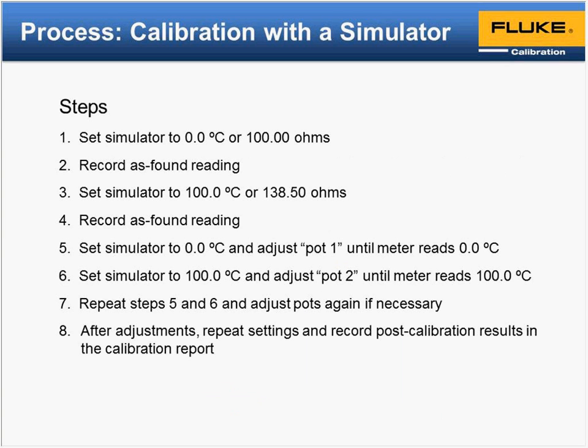Establish the connection. The routine is pretty easy in our example. Again, we're only checking 2 points, the 0 and 100, and that was our criteria for our example here. One thing that's really important as you're going through any calibration is to record your as found readings. So next we're going to set the simulator to 0 C. The simulator now is going to generate 100 ohms, and we'll record that as found reading. Then we'll move to 100 degrees C, or roughly 138.5 ohms. Again, those are the ohm values based off of a typical DIN curve, and record that as well.